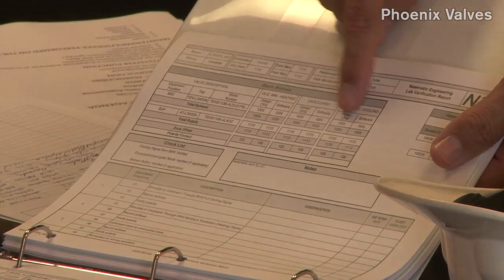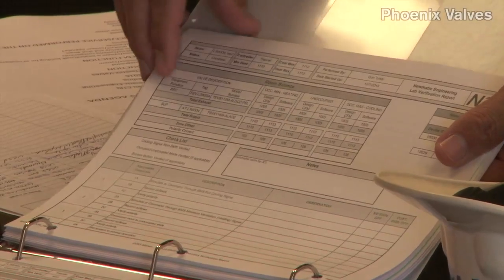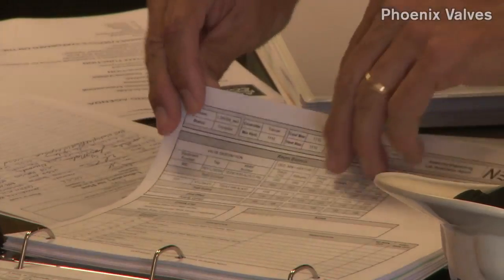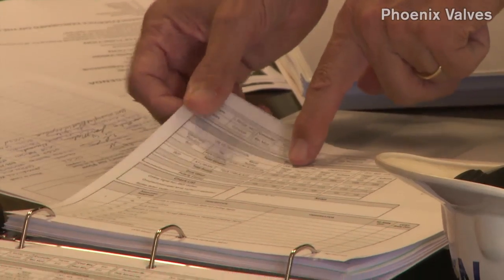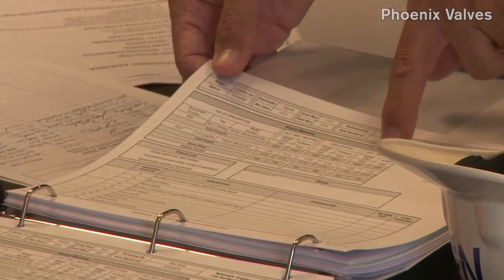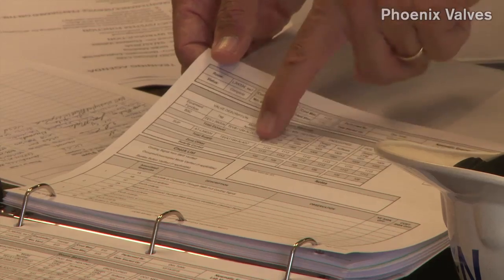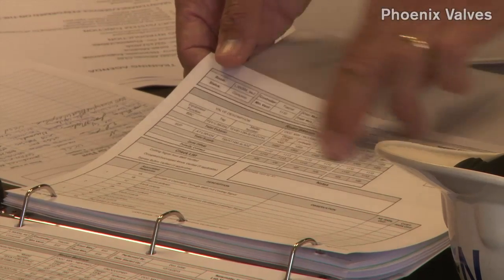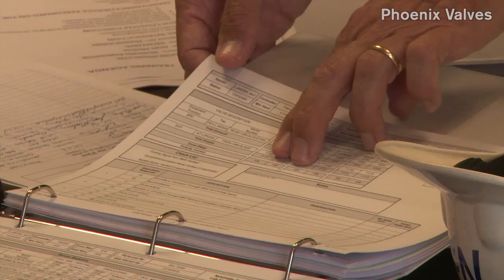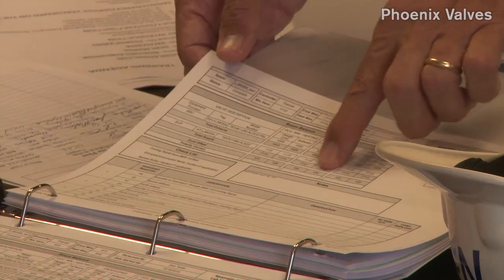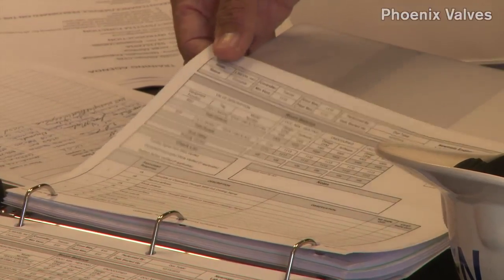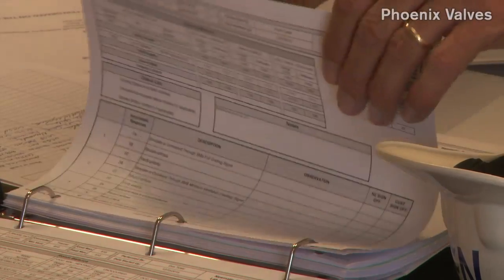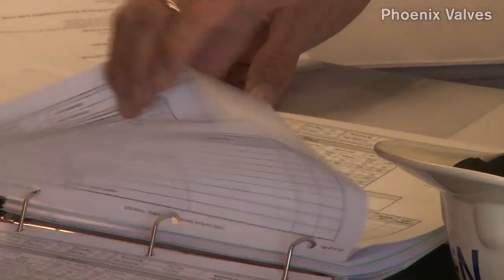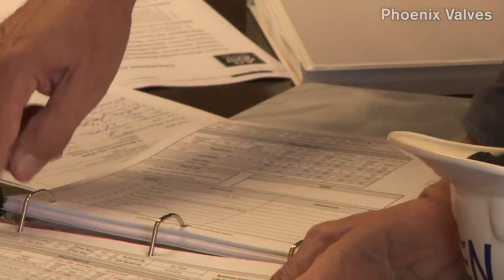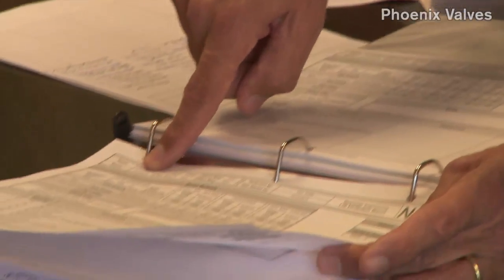But you've got design CFMs there, and we're checking different performance. So the occupied heating, unoccupied, and occupied cooling. The flows are the same for all 3. We got supply and exhaust, and the rooms are supposed to be, by design, about 108 CFM positive. We measured them at 105 CFM positive. The previous room, shown here, is called SW1.